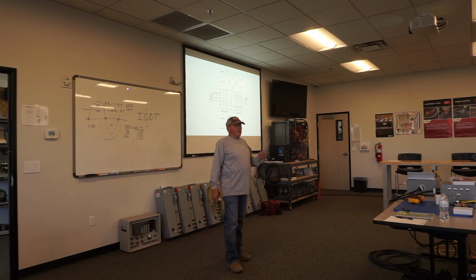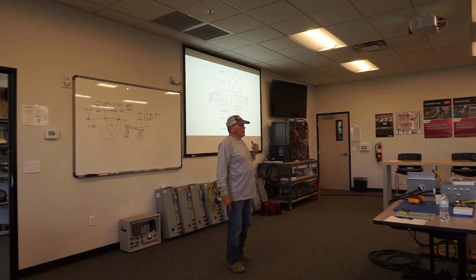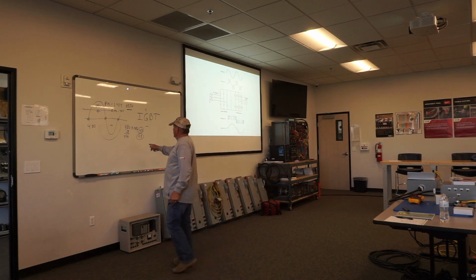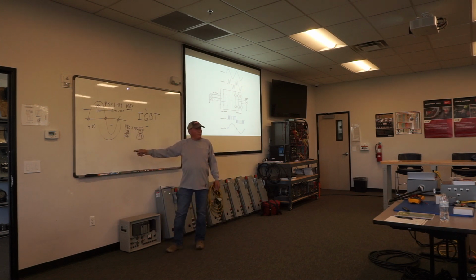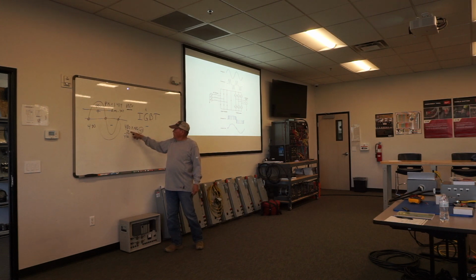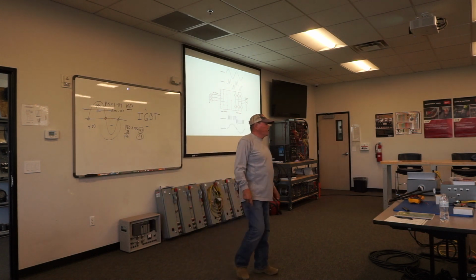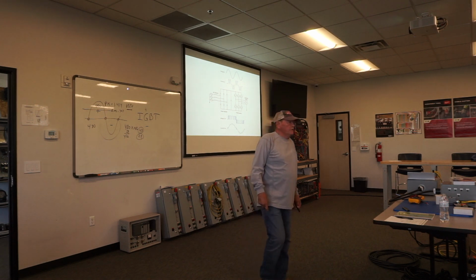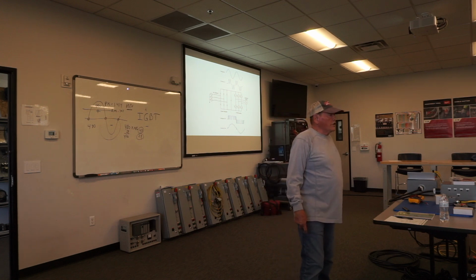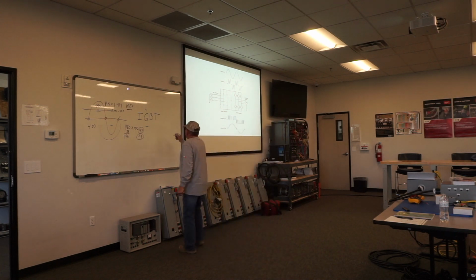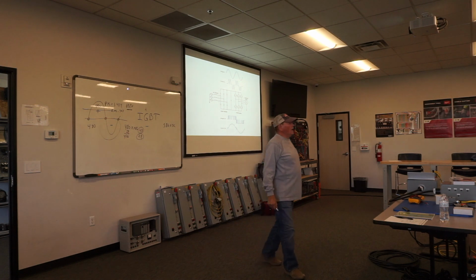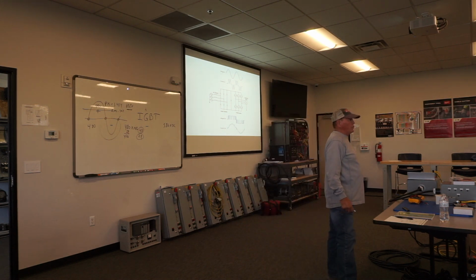But the voltage dips we're seeing out there, of 65 volts, right? If I can only drop 24 volts, and I'm dropping 65 volts, I'm down to 415 volts now. What's 415 volts times 1.414? 586.8. 586, right? So now I have an issue where the first thing the drive is going to do is trip out on low voltage. And if it lasted too long, it could overheat and cause the drive to trip out on overtemp.